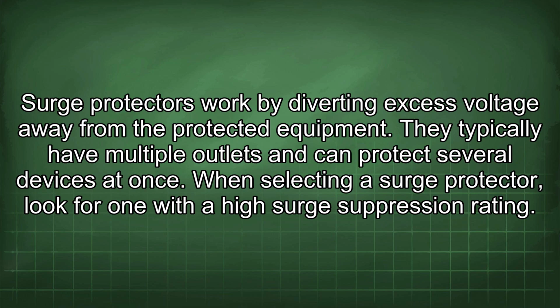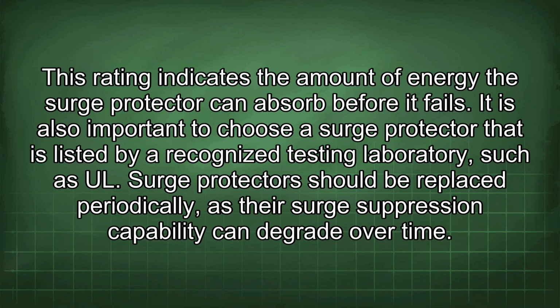When selecting a surge protector, look for one with a high surge suppression rating. This rating indicates the amount of energy the surge protector can absorb before it fails. It is also important to choose a surge protector that is listed by a recognized testing laboratory such as UL.